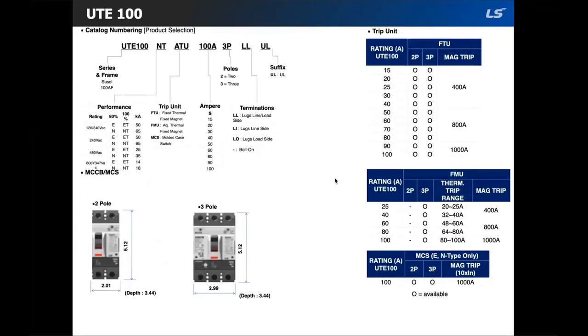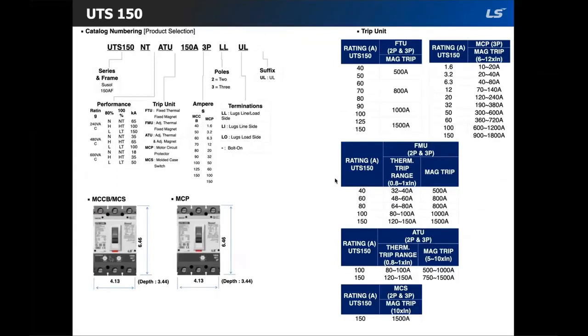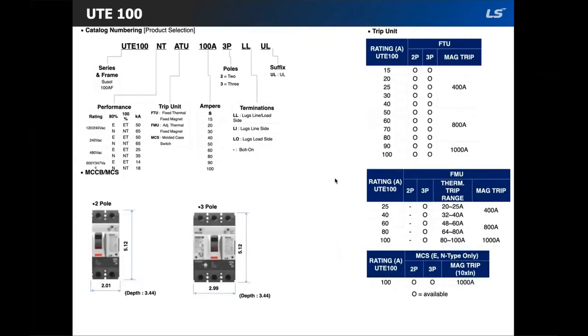Okay, so the first frame size in the MCCB line is the UTE 100. As you can see, there are 4 performance ratings. The 80% continuous rated are the E and N, and then their 100% rated counterparts are ET and NT. And for this particular frame size, there are 3 trip types available. The first one is the FTU, which would be your fixed thermal and fixed magnetic. Then there is an FMU, which would be adjustable thermal and fixed magnetic. And then there is an option for MCS with a fixed 1000 amp magnetic trip unit.